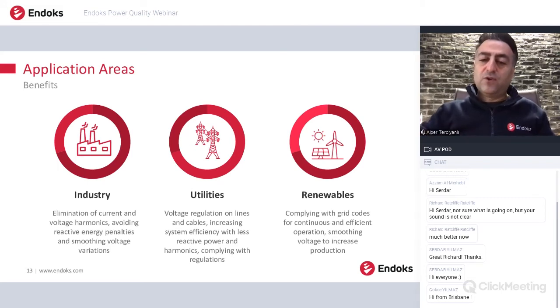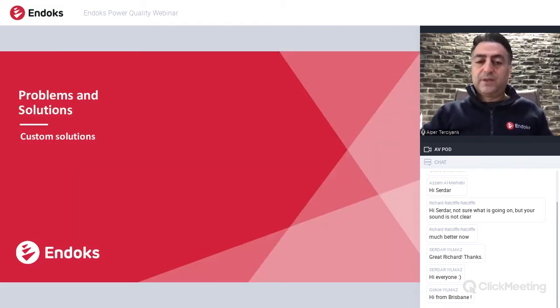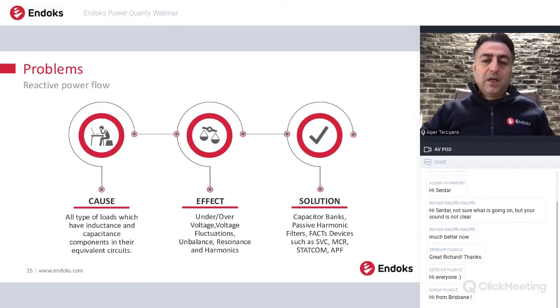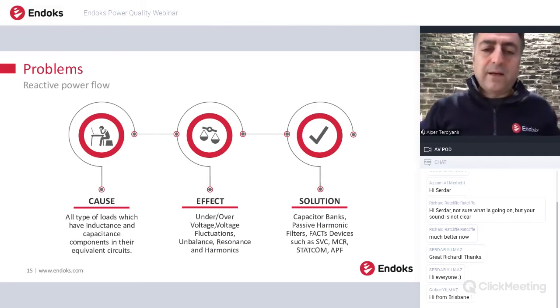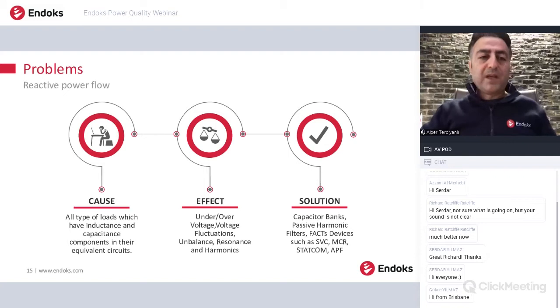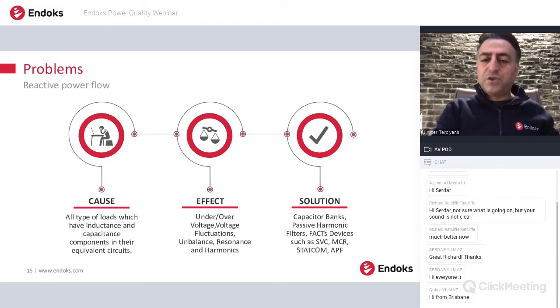So for renewables, the power quality solutions are also very important. And what are the problems and the solutions I would like to tell about? First of all, as I said, even the reactive power flow is not defined as a sole parameter in the standards. Since the voltage regulation is a direct effect of reactive power flow, and losses also are a direct effect of reactive power flow, I would like to take reactive power flow as one of the main problems.